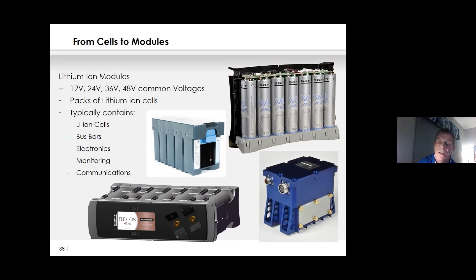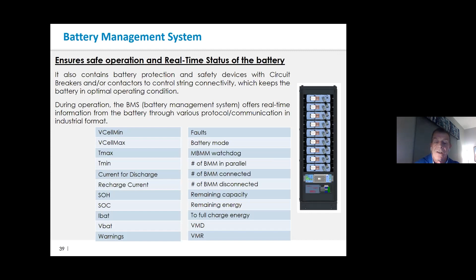The battery management system is a little easier to handle for VRLA batteries. It lets you monitor different aspects of the lithium ion system itself, like the voltage of the cells, their minimums and maximums, number of faults, remaining capacity, discharges, and remaining energy. One key advantage of lithium ion is its ability to discharge and recharge thousands of times, an order of magnitude better than VRLA batteries, which typically run maybe 95 to 150 full discharge-to-recharge cycles.